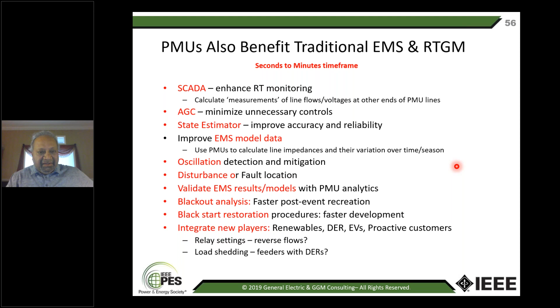So if you had PMUs at every substation, you really have a state measurement rather than a state estimator. You can improve EMS model data. A lot of our EMS models have impedances defined from whatever your books, your Westinghouse T&D book, say. But now with PMUs, you just put a PMU at two ends of a line, you have voltage and current here and voltage and current there, and you know exactly what the impedance is because they're time synchronized. So you can monitor impedances over time, and there are many other things that can benefit from PMUs in existing EMS capabilities.